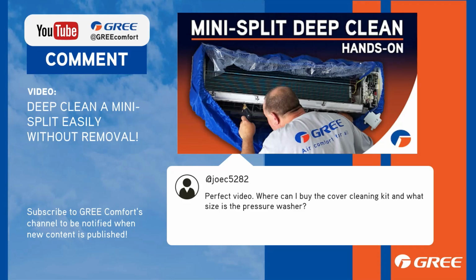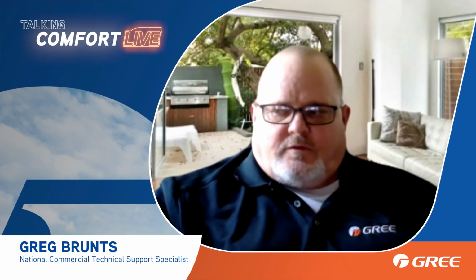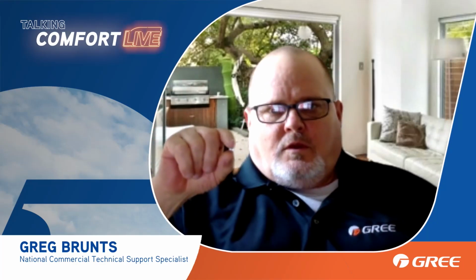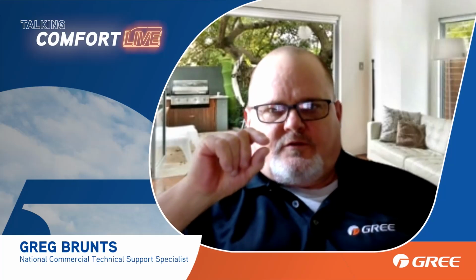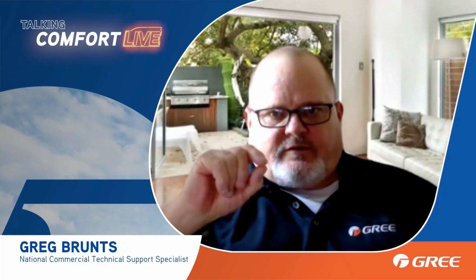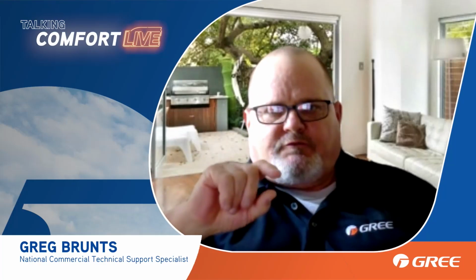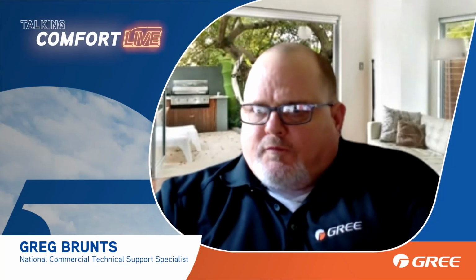The biggest thing I can say about mini splits and your inspection piece, like I showed in that video, is looking at that blower wheel. When that blower wheel starts getting some buildup, that's when it's time. You're losing efficiency at that point, whether or not it's keeping the unit from working right doesn't matter. Once you start getting a decent amount of dirt buildup on that blower wheel, now it's time.